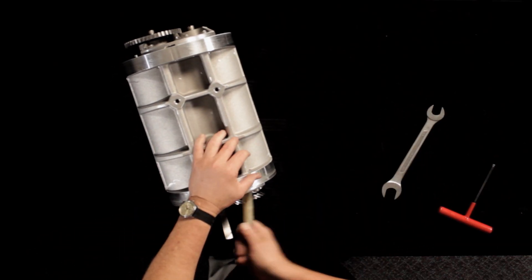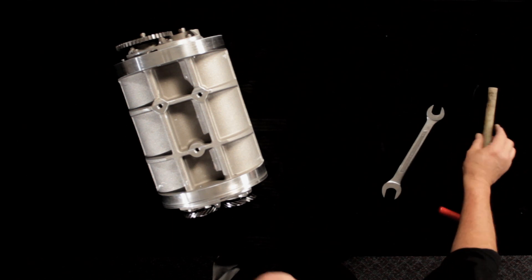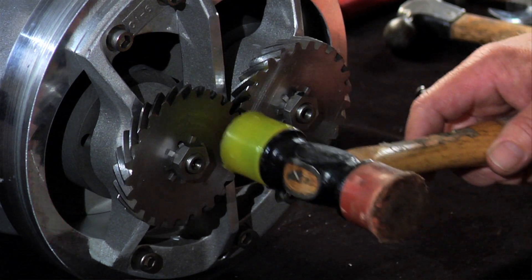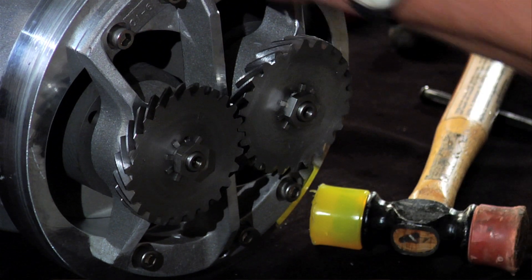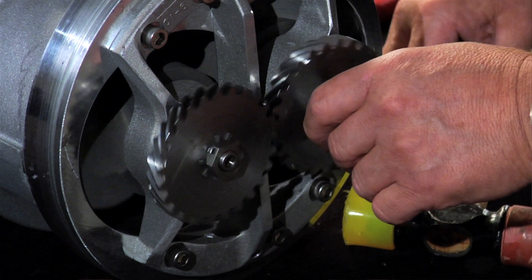Once the gear is tightened, remove the block and the shim. The rotors should rotate freely without rotor-to-rotor contact or scrubbing. If the rotors make contact, remove the second gear and repeat the steps for setting the clearance.